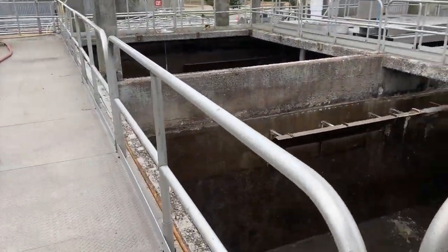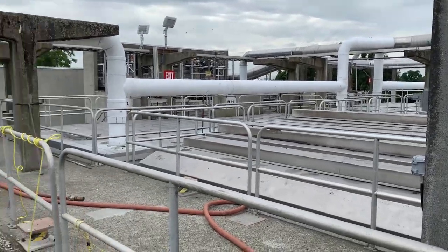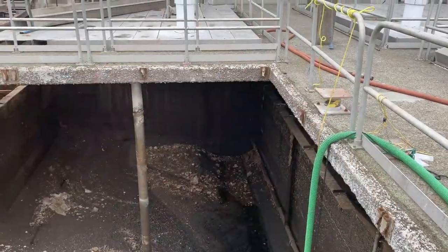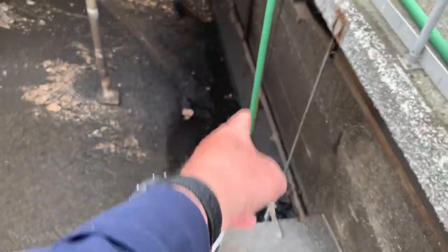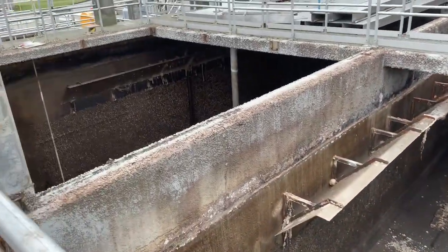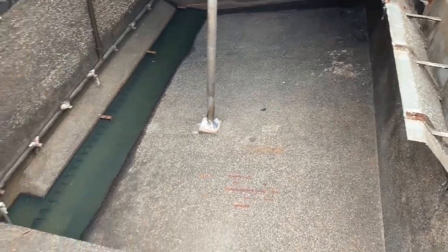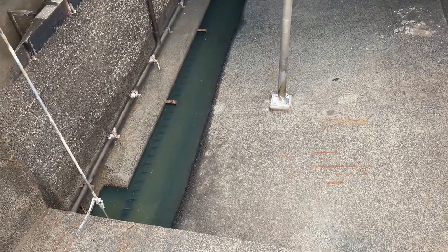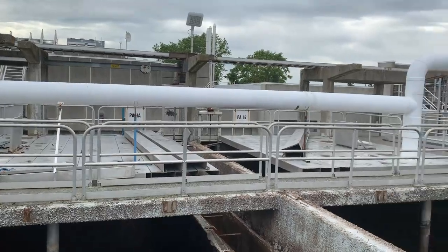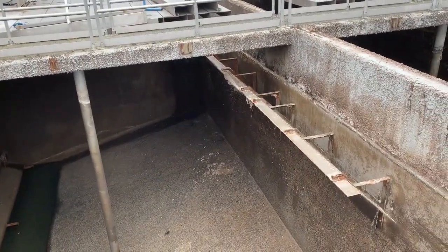This is a grit tank empty for servicing. Bubbles come out of a long pipe along the bottom to circulate the water, and the heavier grit accumulates at the bottom — that black sand is the grit. There's also a mountain of grease in the background; grease is a reality we deal with a lot. In a cleaned tank you can see the augers — big screws that drag the grit along to one end. The large white pipes remove foul-odor air, because H2S is released when you aerate sewage.